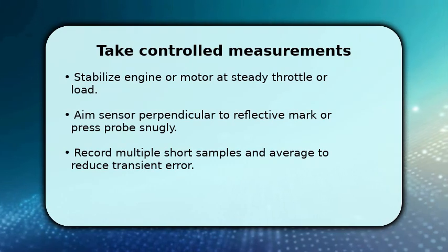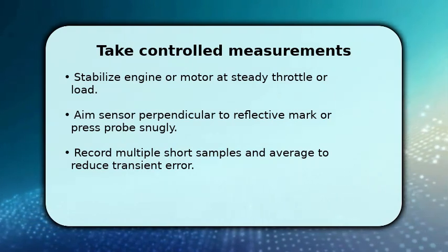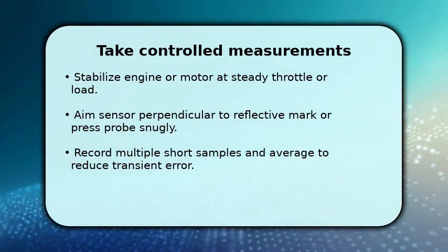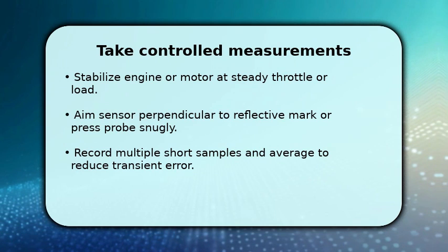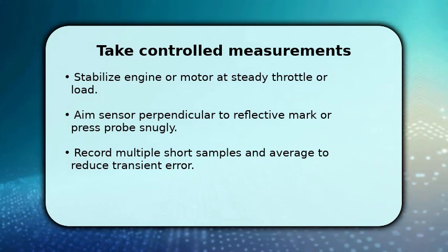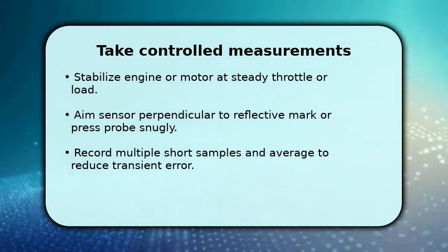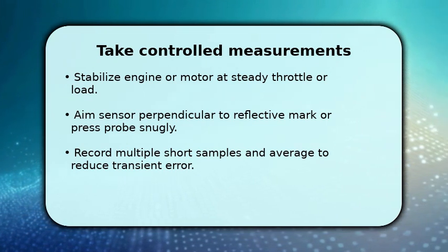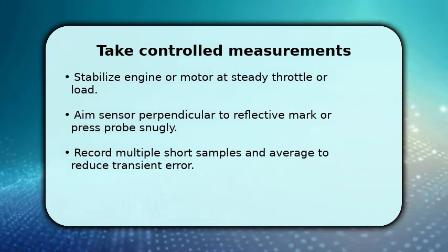You now run the machine to a stable operating point and approach the marked area with the tachometer. For optical units, hold the beam perpendicular to the reflective tape and keep a steady hand. For contact units, press gently until the probe sits flush and avoid lateral force.